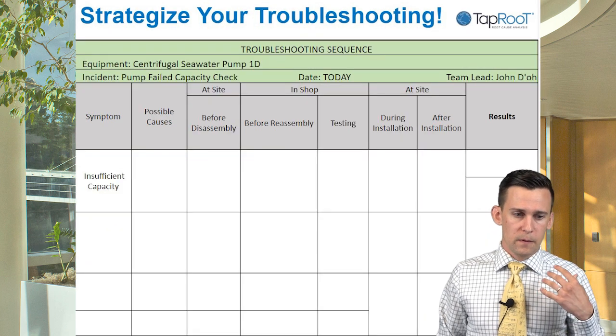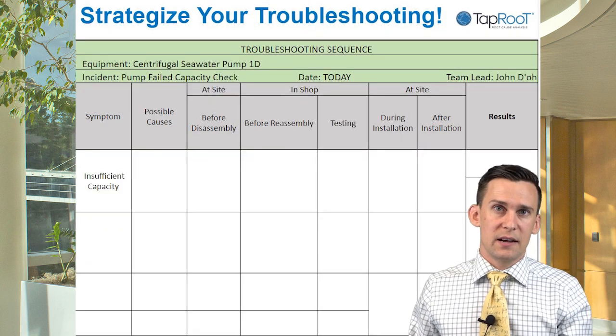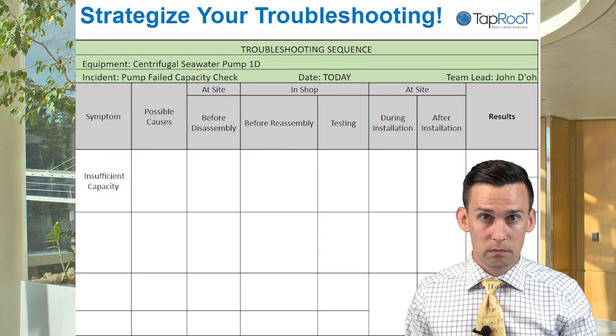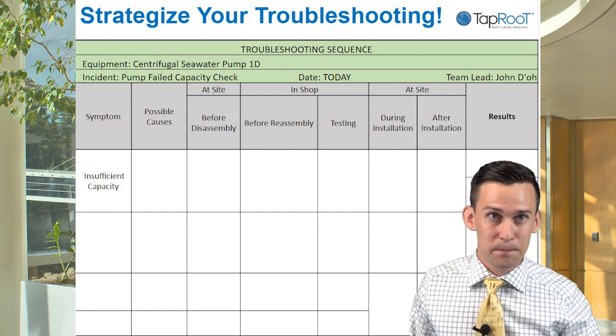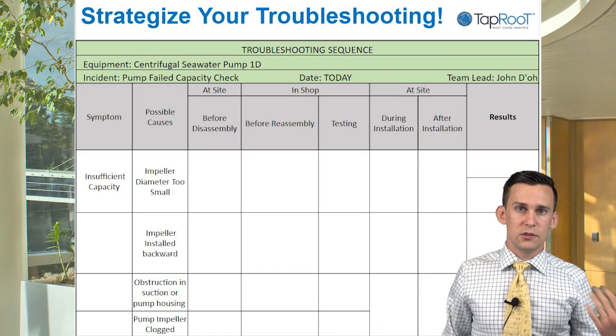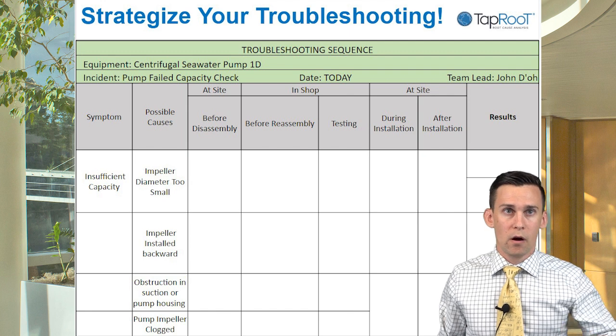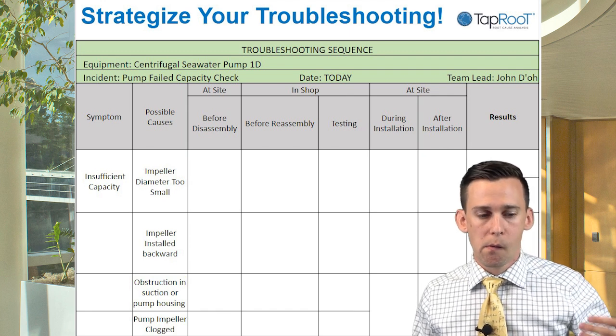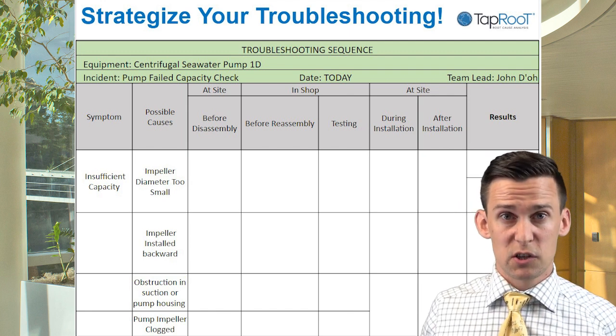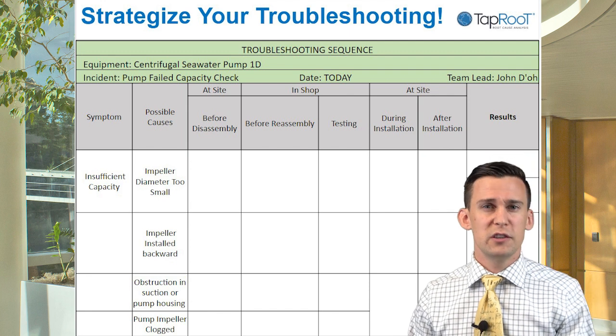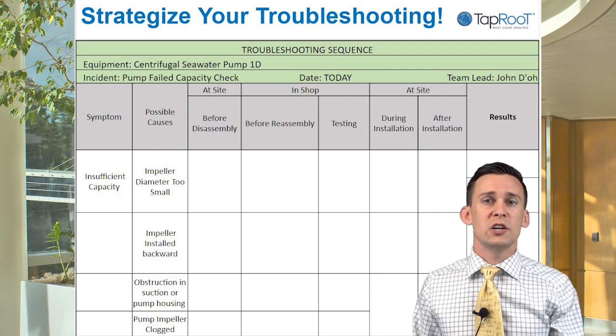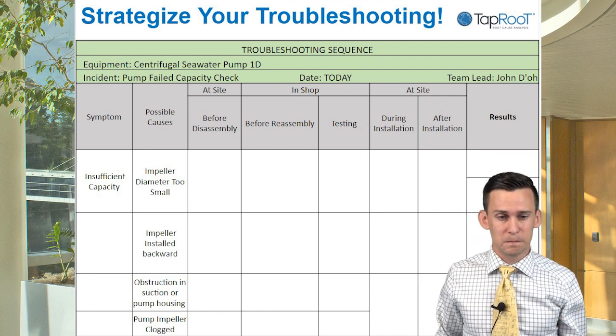So let's say for this insufficient capacity, there's only so many places we need to check for data. Here are the possible causes we found: our impeller diameter was too small, the impeller itself was installed backward, and there might have been an obstruction. These are the things we couldn't prove, or that we didn't already check, without tearing the pump apart.